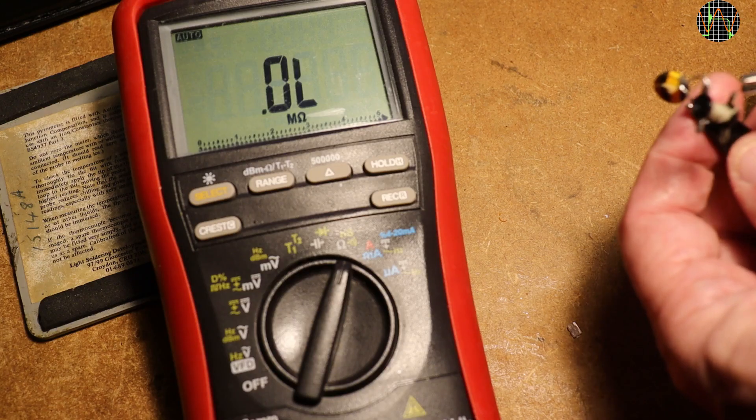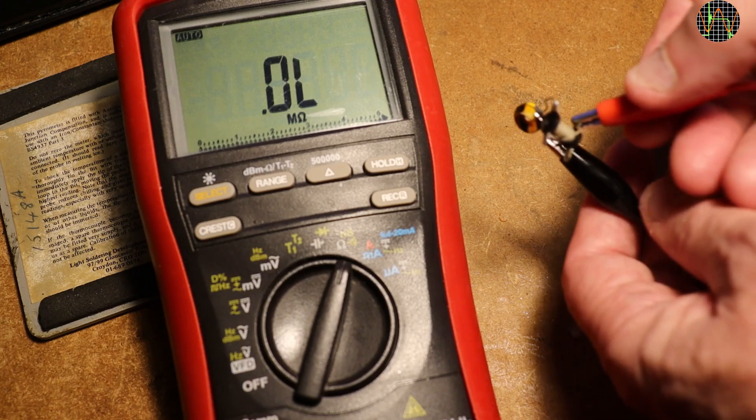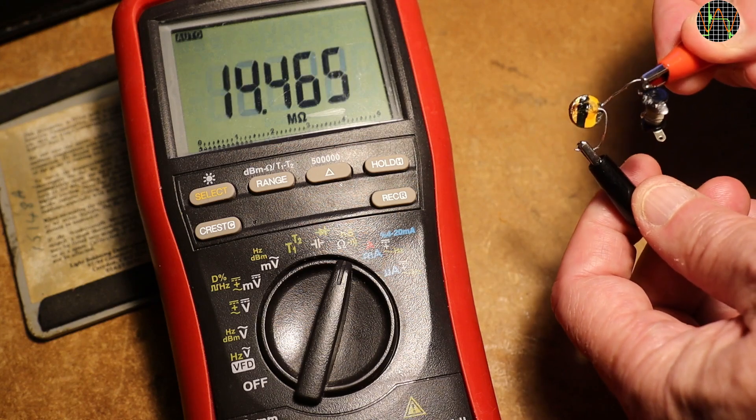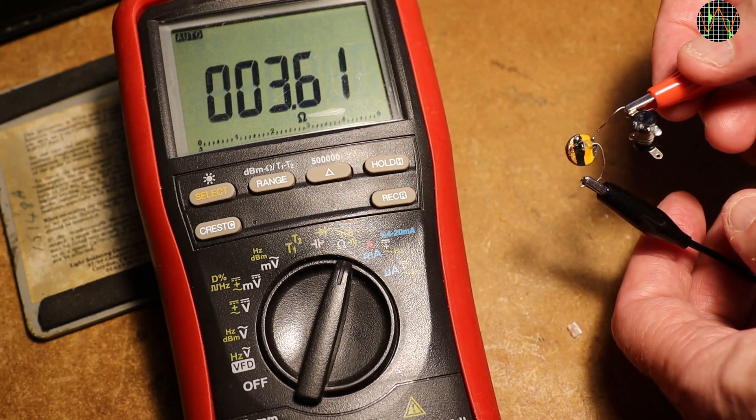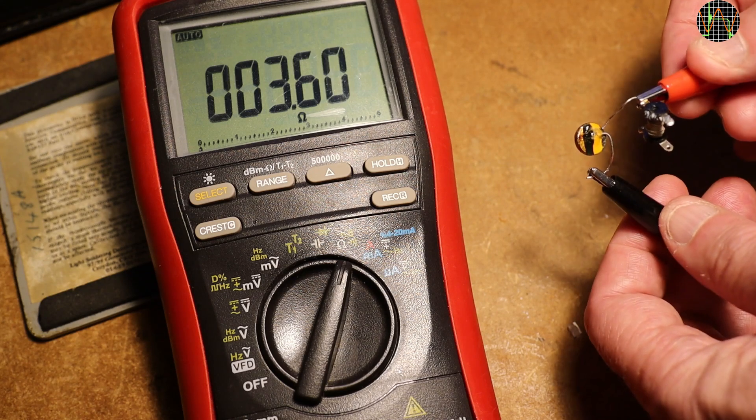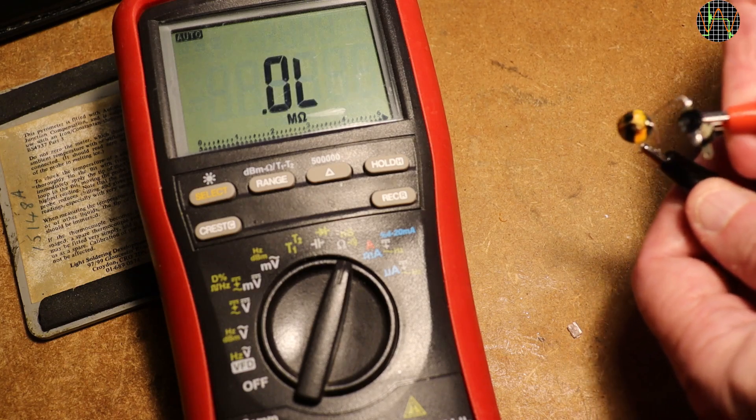So what resistance was in there? Oh shoot, I must have somehow broken it during the extraction because it now reads infinite. I should have measured the whole assembly before trying to unstick it from inside the instrument. Well, at least the disk itself has 3.6 ohms so it is the wire wound part that is broken.